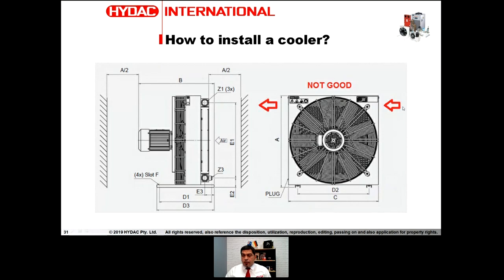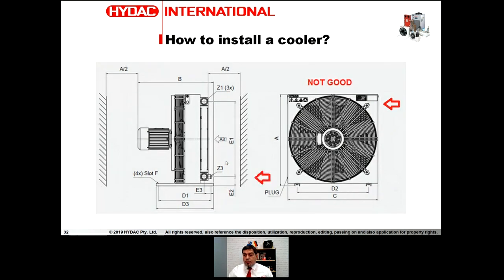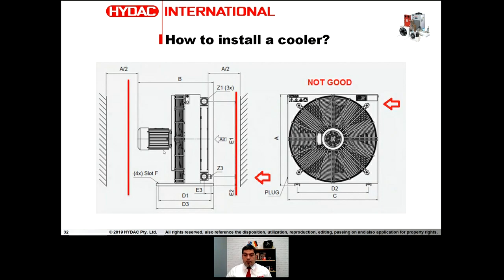What is not good: entering and exiting at the top — you only use the top part of the cooler and can lose up to 50% of cooling power. Also bad: ignoring the A2 clearance distance with a wall too close at the back, or a constraint at the front. Finally, entering at the top and exiting at the bottom is also not recommended — heat and temperature rise, so you're not using the cooler effectively. And always remember: the cooler has to breathe — never install it in a confined environment.